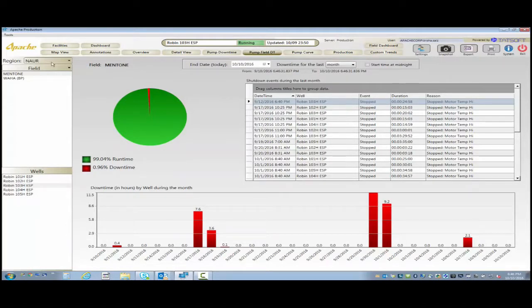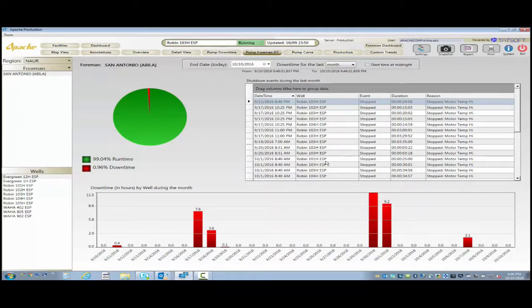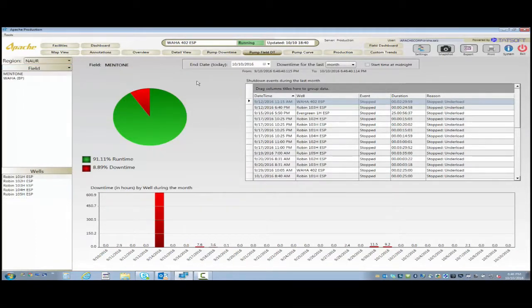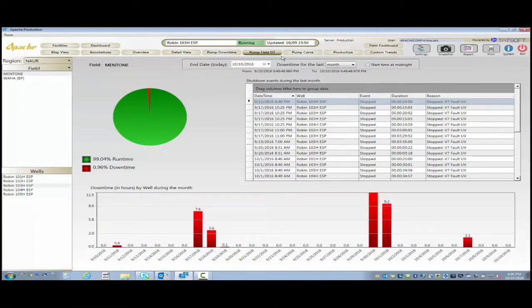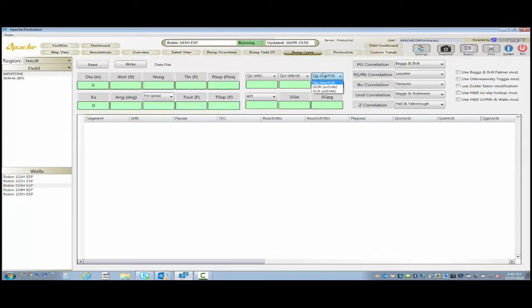A couple of things you may notice on here was power failure. What we found out in our quick analysis was the fact that the power company was sending us really dirty power. We're having significant issues in a couple locations. We're actually able to go back to the power company and say, clean it up. Help us out. You're causing problems.